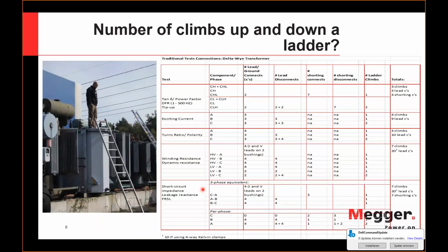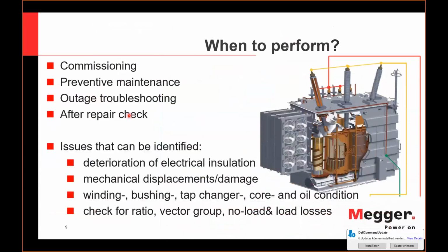Statistics show that a lot of accidents in the substation environment occur just because test personnel must climb up and down the ladder on the cover of the transformer many times to interconnect different test circuits, make a short, make an open test, make the bushing test. You always need to rewire your leads repeatedly.